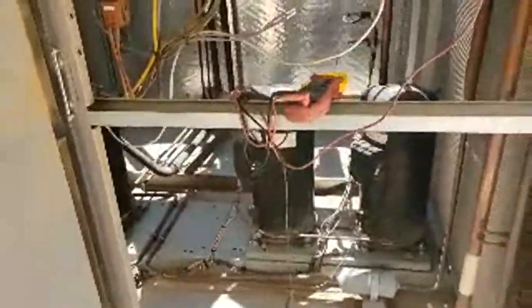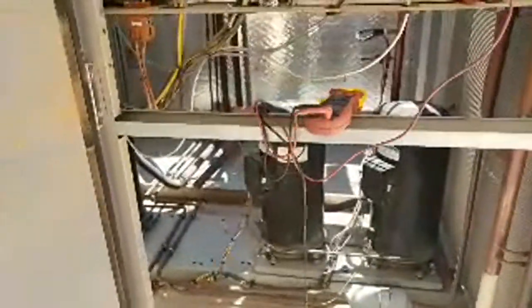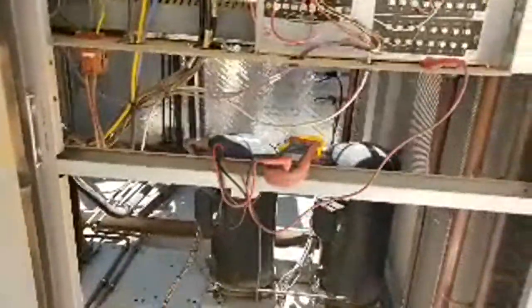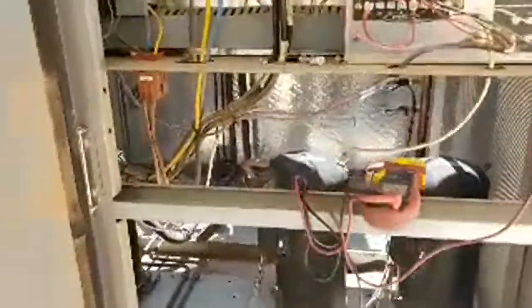And of course, if it thinks it's getting a call for cooling, and the temperature's below 55 or so, it'll open up. But if it's in economizer mode, it'll stop the compressor from coming on until the second stage input goes on. So if it's cooling, running all the compressors like normal, but the damper's open and it's not supposed to be, then I'd be checking your indoor air quality terminal and your minimum damper position screw, see what those are at.